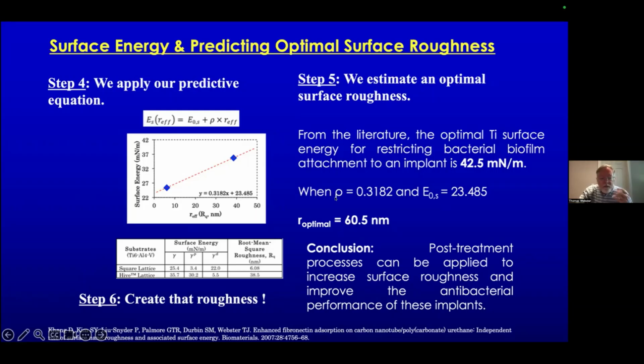We have a fudge factor. The Greek letter rho is 0.3182 for titanium. We have different numbers for different chemistries. But for titanium, which we're doing here, we followed this for our screw example that I talked about, which is in 30,000 humans and is not failing. Take that number, put it in right here. Then all you have to do in this equation, it's a line equation, is calculate what the roughness, REFF, should be to transition your material into one that has a surface energy of 42.5.